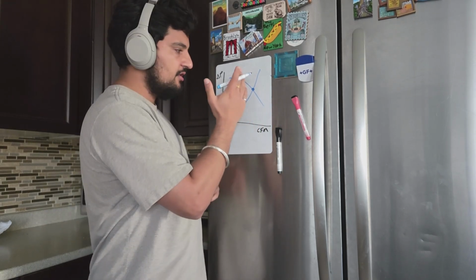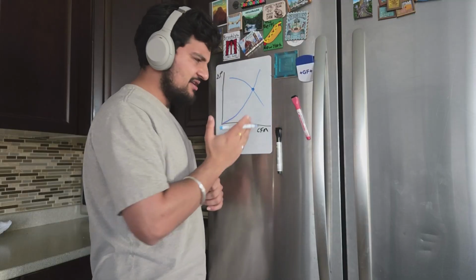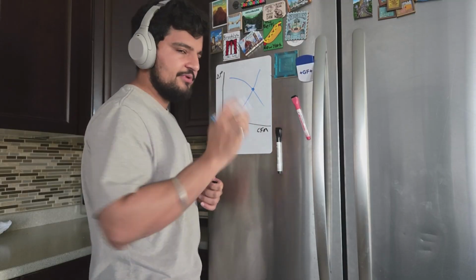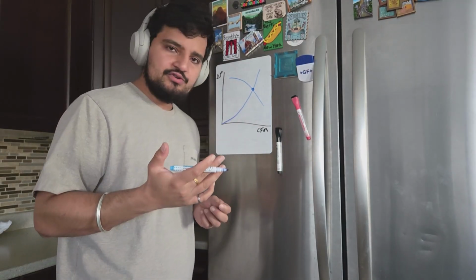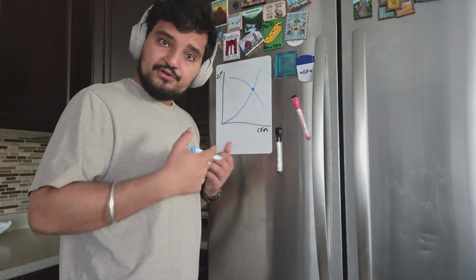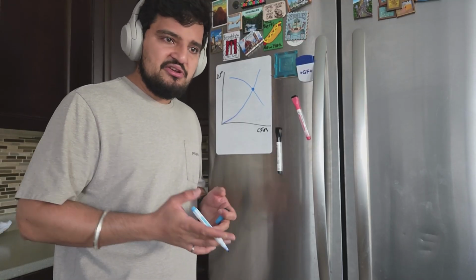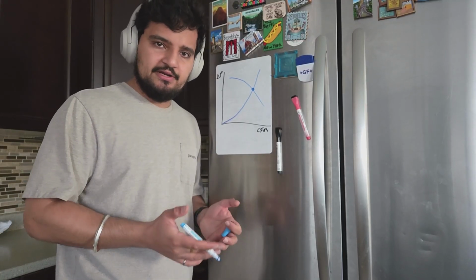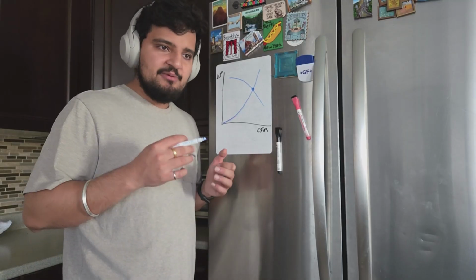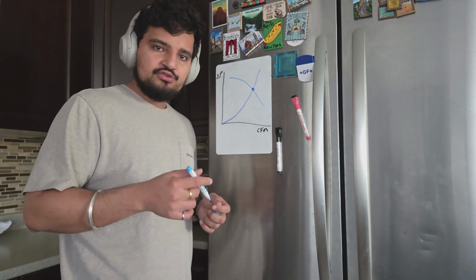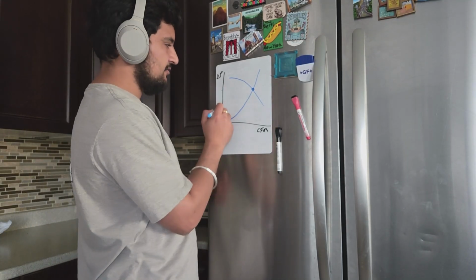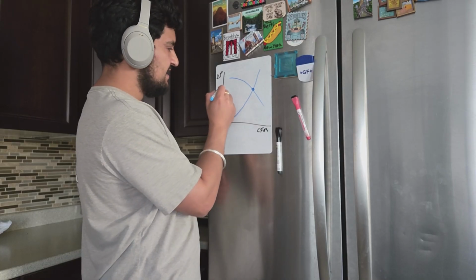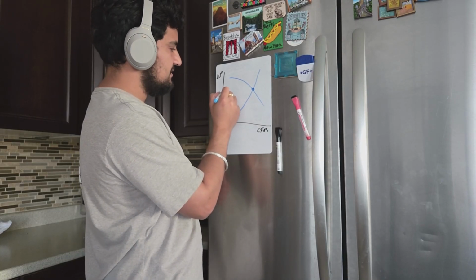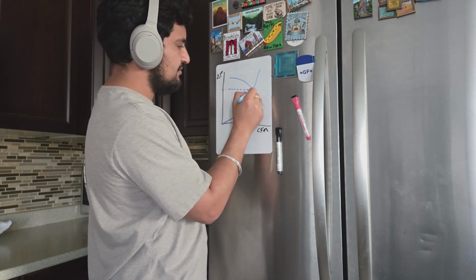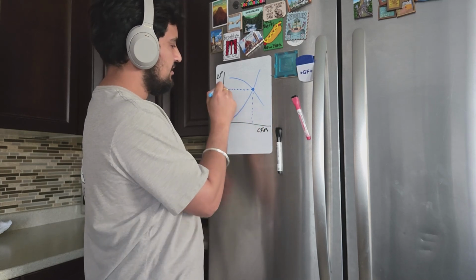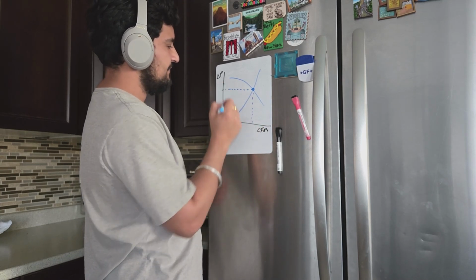Let's say once you've installed the air handling unit when the house is brand new and it works perfectly fine at this operating point. And in the future, maybe your filters have gotten dirtier. Maybe something broke in the ductwork and it's created obstruction. Maybe the cooling coil is very dirty. So your pressure has actually increased a little bit in your system. So what's happened is your pressure has gone from this. So this is your original operating point. Now your pressure is maybe somewhere here, right?